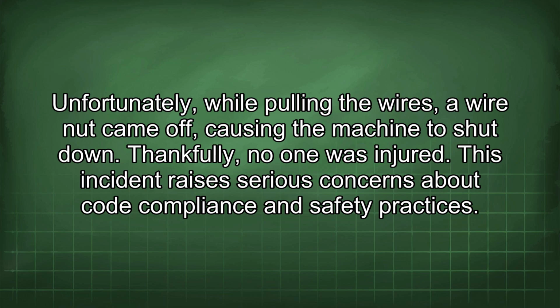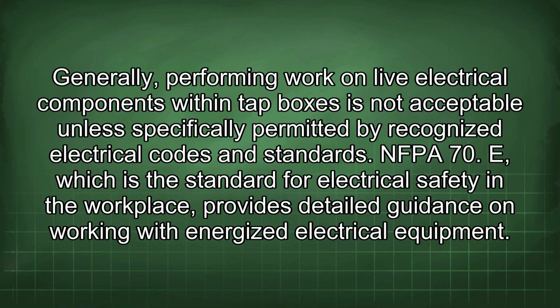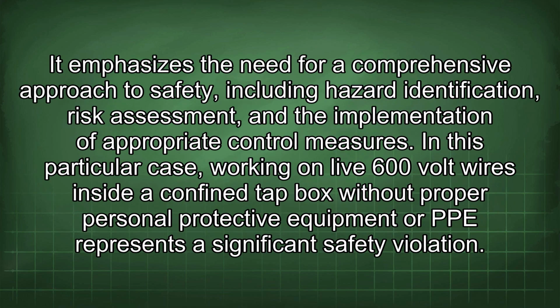This incident raises serious concerns about code compliance and safety practices. Generally, performing work on live electrical components within tap boxes is not acceptable unless specifically permitted by recognized electrical codes and standards. NFPA 70E, which is the standard for electrical safety in the workplace, provides detailed guidance on working with energized electrical equipment. It emphasizes the need for a comprehensive approach to safety, including hazard identification, risk assessment, and the implementation of appropriate control measures.